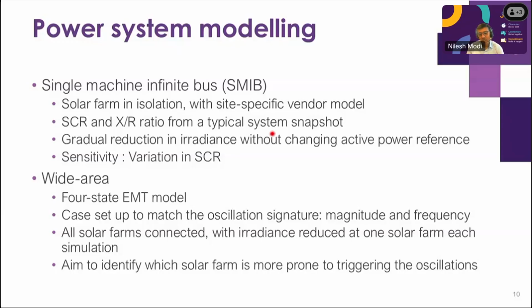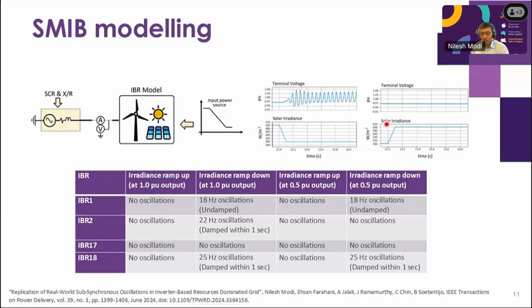Then we started looking at the wide area simulation. We looked at the 4-state EMT model, which we have. We set up the case to certain conditions and started playing with the irradiance change at a number of IBRs to see which one is actually causing it. We looked at one solar farm at a time, and there was a consistent observation: when we changed this slow irradiance in one of the IBRs, it showed the oscillation on the grid, and it was propagating all the way in the West Murray area.